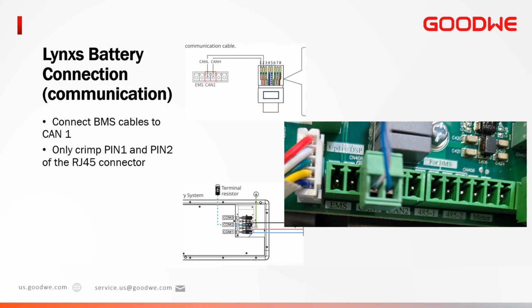The next step in the battery connection is the communication wires. For Lynxs batteries, the connection is an RJ45 to COM port 1. Don't forget to install the terminator on the COM 2 of Lynxs battery. On the other side, or inverter wire, you're going to use the 2-pin terminal included, and you're going to connect to pin 1 and pin 2, which is the CAN 1 connection.